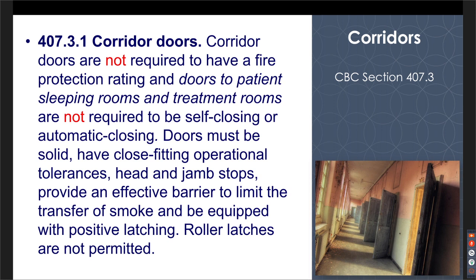The doors in the corridors, keep in mind this section here is if the building is fully sprinklered. So if the building is not fully sprinklered, there'll be some other provisions that come into play, but if the building's fully sprinklered, the corridor doors do not have to have a fire protection rating unless they otherwise need it, like an incidental use room, for example.